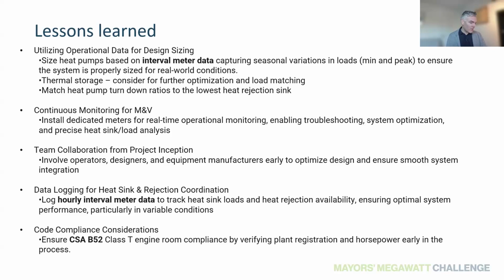One of the things we touched on here was the turn down of the heat pump, and one of the specifications that wasn't available was that specific turn down. So when we went to size this equipment, we sized it for the peak. Without having thermal storage available, either on the cold side with something like a glycol ice battery to draw from whenever heat was demanded but not necessarily in the ice plant, or having enough thermal storage on the high side to discharge heat whenever it was available and store it for future use, having that misalignment in loads is certainly a challenge.